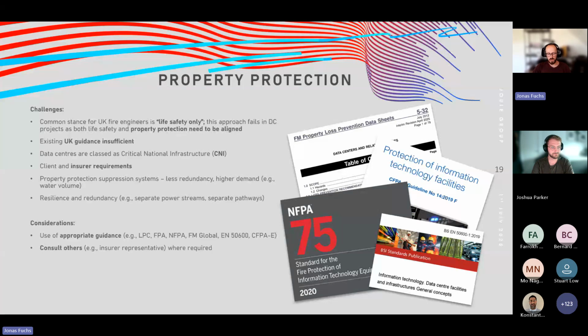When it comes to property protection suppression systems, they are often seen as less reliable or less stringent in design compared to life safety, due to standards requiring less redundancy, but they often require higher demand when it comes to water volume and design densities. Overall, one item that's quite often not well picked up in earlier design stages is the resilience and redundancy when it comes to power streams and separate pathways. Effectively, a data center is designed as a series of compartments, where a failure in one should not impact the others.